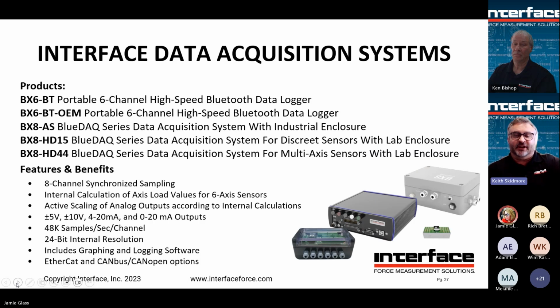Data acquisition systems. Again, say you're monitoring, you may want to actually log and maybe say have multiple devices, maybe a position sensor, accelerometer, a load cell. Might want to monitor all of those things and have them synchronous and have them logged on the same plot. Say there's some motion being controlled, lifting and moving an article, maybe certain parameters that entire motion must stay within. You might want to log and monitor that and then do some analysis afterwards.